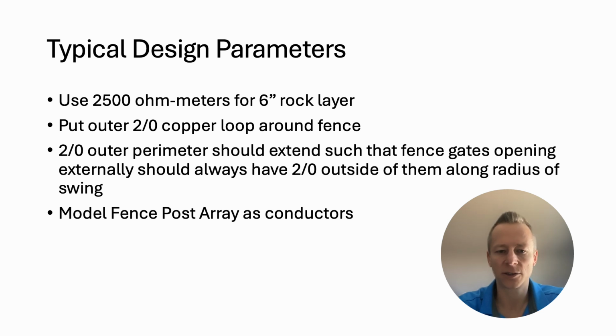Even if you spec it for the contractor to install it to swing inwards, you don't know if it truly gets installed that way, or if somebody misses that, or later they add it and change the gate and make it swing outward. We just always design it so the gate can swing out and still be safe. You want to make sure that's all modeled in your study. And then we also model all the fence posts as ground rods because they get tied back in. So your fence acts like a bunch of ground rods as well.